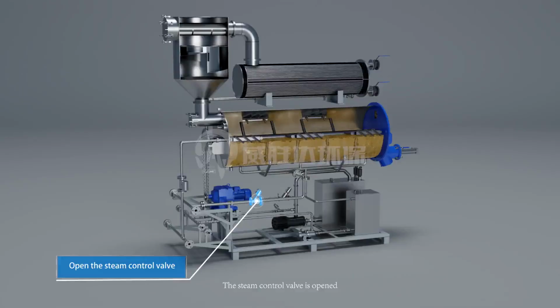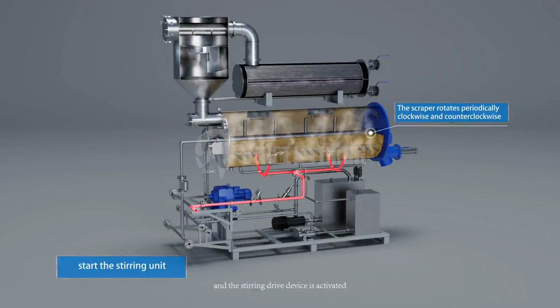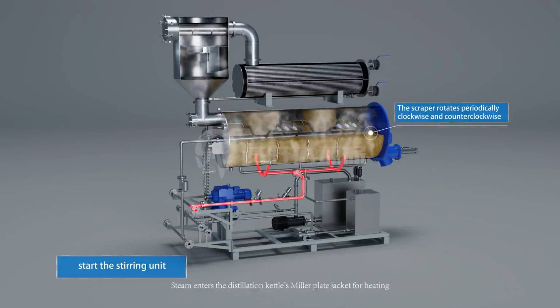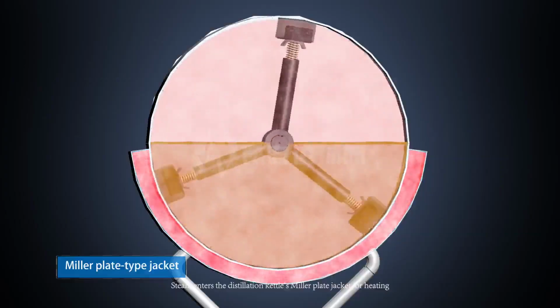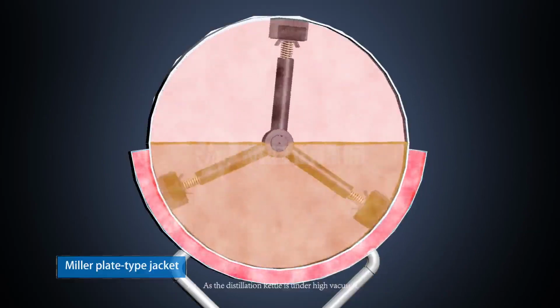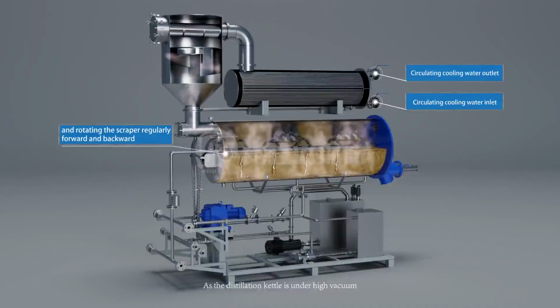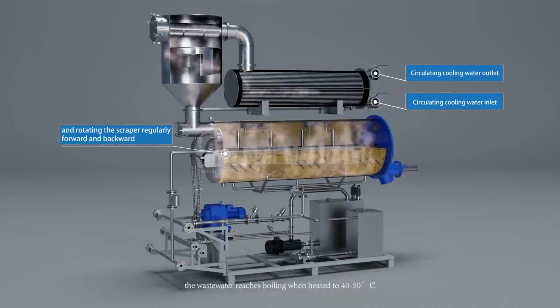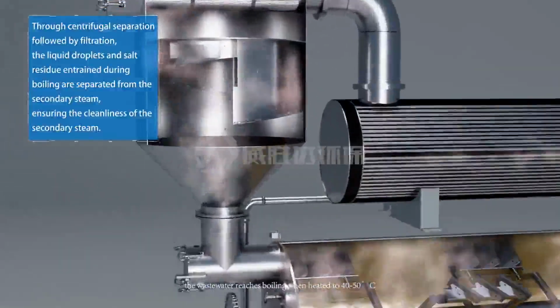The steam control valve is opened and the stirring drive device is activated. Steam enters the distillation kettle's Miller plate jacket for heating. As the distillation kettle is under high vacuum, the wastewater reaches boiling when heated to 40 to 50 degrees Celsius.